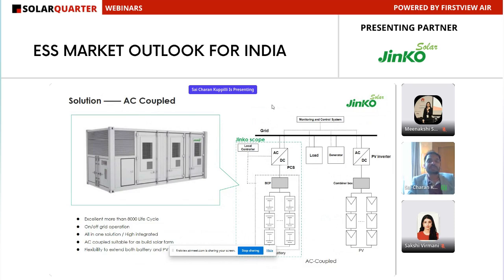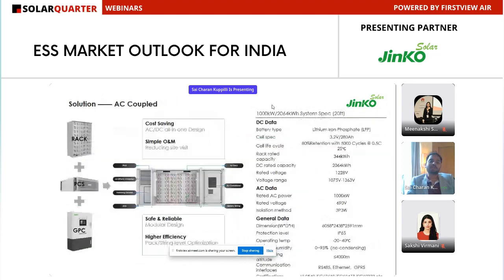So we can see a better life cycle of these products, not less than 6,000 cycles, which means if we consume one cycle per day, it's going to cross around a minimum of 10 years. That's the actual benefit with these AC coupled systems. As I was explaining, this is the layout of a simple container of an AC coupled system, and within this, the center section is completely the battery bank part.